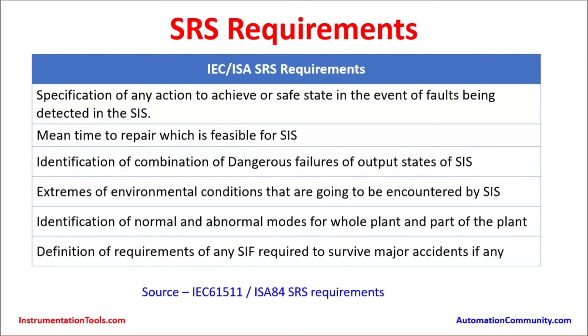Mean time to repair (MTTR) feasible for the facility must be identified. Dangerous combinations of output states of the SIS must be documented. Extreme environmental conditions encountered by the SIS must be noted. Normal and abnormal operating modes for the whole or part of the plant must be identified. Finally, requirements for any safety instrumented functions required to survive major accidents must be defined. This concludes the complete steps and requirements based on IEC 61511 and ISA 84 for developing the SRS. Thank you.